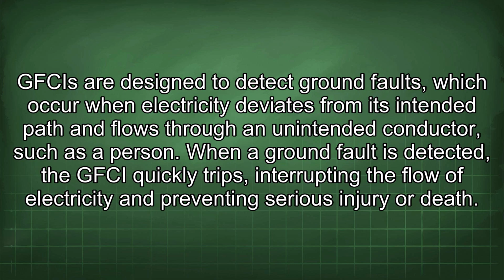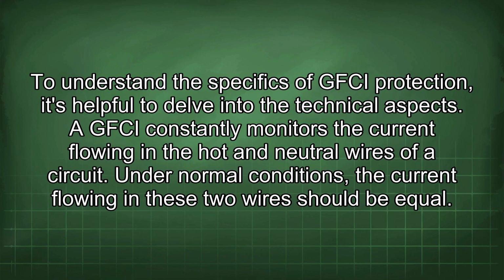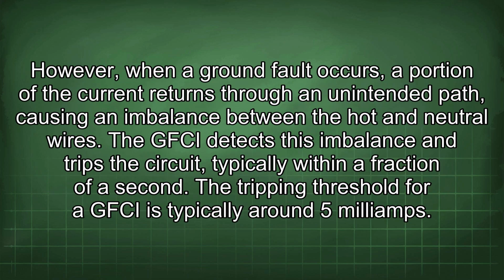When a ground fault is detected, the GFCI quickly trips, interrupting the flow of electricity and preventing serious injury or death. To understand the specifics of GFCI protection, it's helpful to delve into the technical aspects. A GFCI constantly monitors the current flowing in the hot and neutral wires of a circuit. Under normal conditions, the current flowing in these two wires should be equal. However, when a ground fault occurs, a portion of the current returns through an unintended path, causing an imbalance between the hot and neutral wires. The GFCI detects this imbalance and trips the circuit, typically within a fraction of a second.